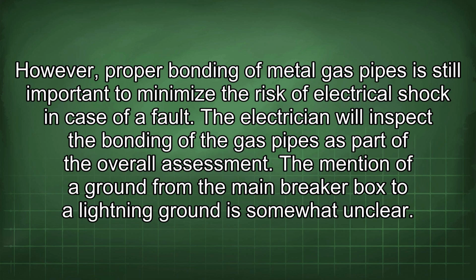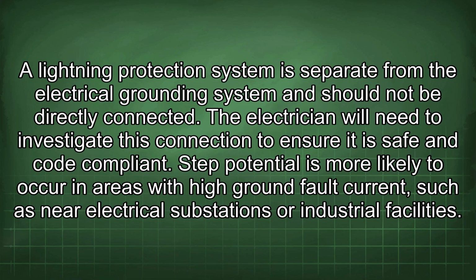The mention of a ground from the main breaker box to a lightning ground is somewhat unclear. A lightning protection system is separate from the electrical grounding system and should not be directly connected. The electrician will need to investigate this connection to ensure it is safe and code compliant.